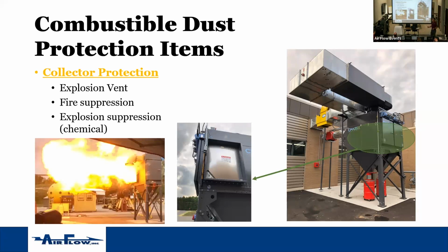So on the body of the collector, you'll end up with that sacrificial piece of metal rated for the P-max of the collector and the KST of the collector. And you'll direct it. I wish I could have gotten this video to play, but it's too big of a file. This is a snapshot picture of what actually happens when an explosion occurs in a collector. All of this is from Fike's facility testing this sacrificial piece itself. And you can see that's coming off a fair distance away, and it's a flame ball. So anything that's in that direction, whether it's a building, people exiting the building on a walkway, a tree, anything that's combustible, we need to make sure we control which direction that goes in.